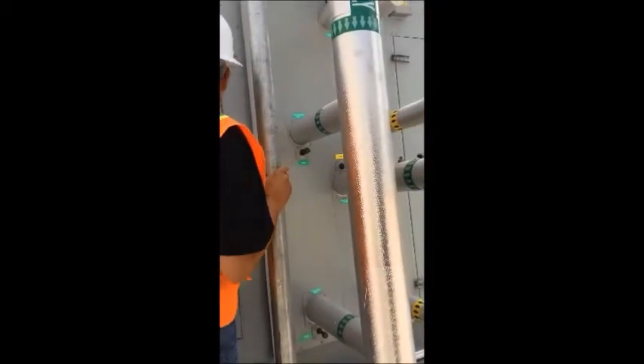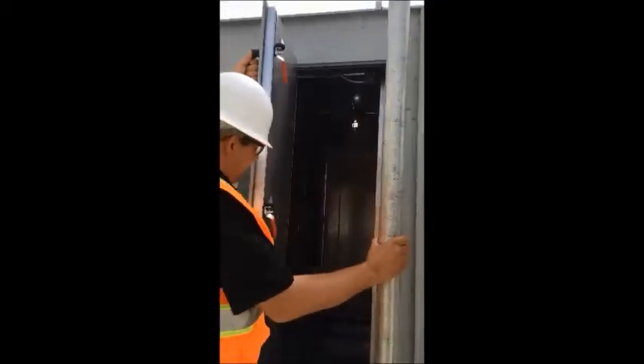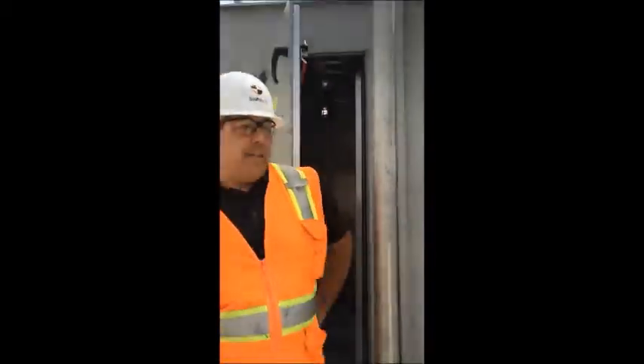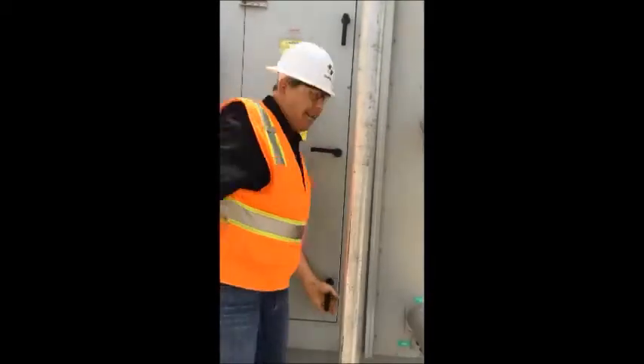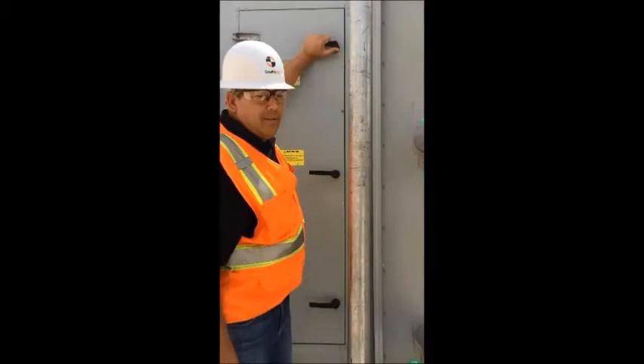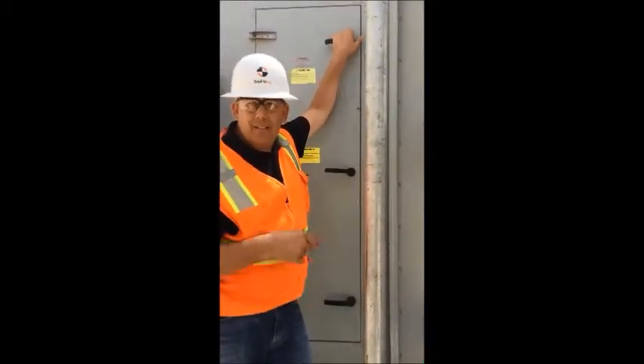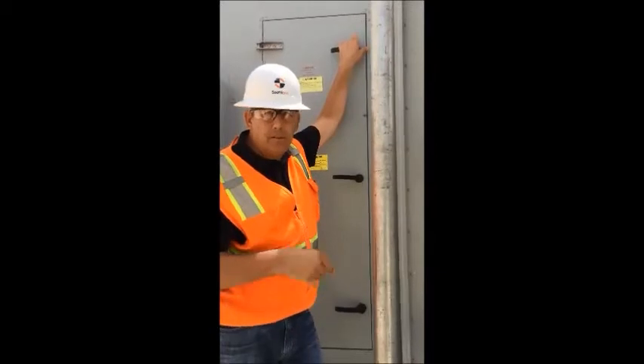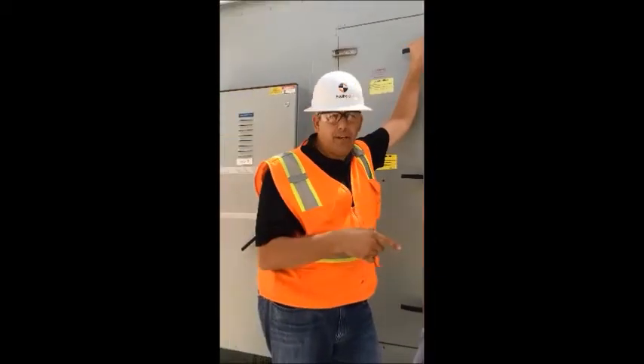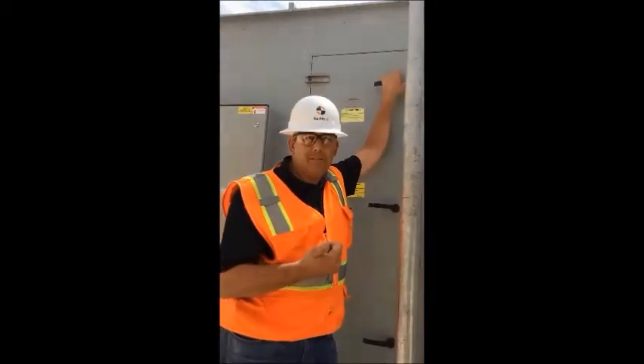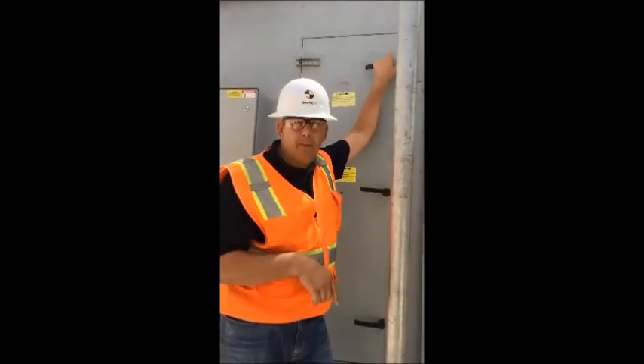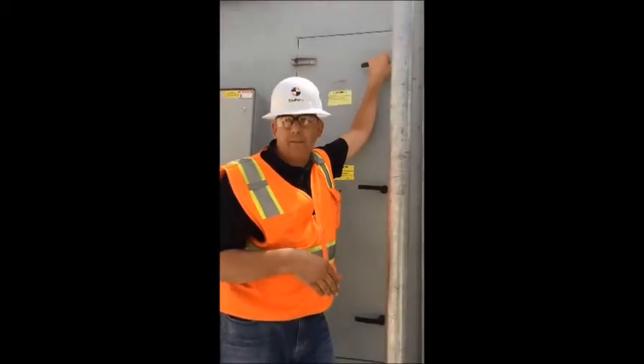Now I put signs on every one of these cabinet doors, but in this one, oh, you got the UV light. UV lights. So there's all your UV lights in there, UV light switches. When you go to work on these units, this door is closed, the UV lights are on. Again, I'll repeat, if you have this door closed and there's power on the unit, 120 volts, those UV lights are on. So when you're working here and you want to do filter changes, you don't want to get your eyes burnt. You want to open up this door. You make sure those UV light bulbs are off as you're working around these fans.